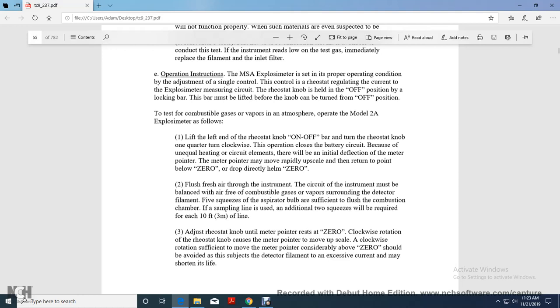The meter pointer may move rapidly upscale with a return to a point below zero, or drop directly from there to zero. Flush very fresh air through the instrument. The circuit of the instrument must be balanced with air free of combustible gases and vapors surrounding the detector filament. Squeeze the aspirator bulb enough to fully flush the combustible chamber. For the sampling line, 2 additional squeezes will be required for each 10 feet of line. Adjust the rheostat knob until the meter points to zero.